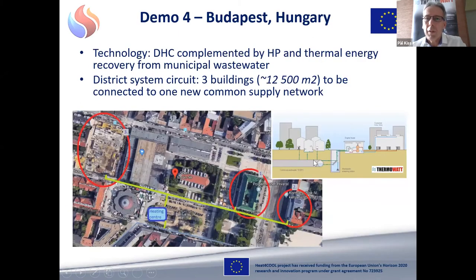That is described in this slide. So we extract heat from the raw communal wastewater flow. In the first stage we screen the wastewater flows, and then we do a heat exchange, and then the heat pump. I had a question on that. So the heat pumps are not special. They are water to water heat pumps, high-grade screw type heat pumps that we use in our installations.